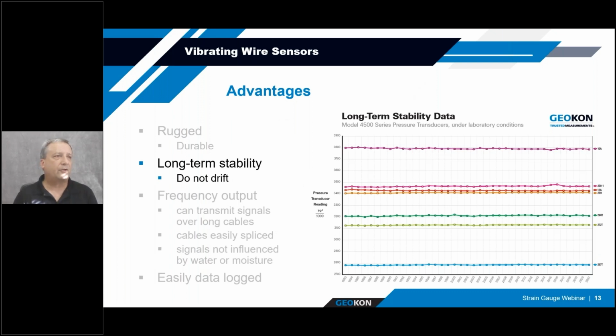Also, they're very stable for long term. Vibrating wires have been shown to provide significant or not changing output for quite a few years. We've got some sensors in the Geokon facility that have been read since the early 80s, shown here on this plot, with very little, if any, trend or drift over time. And we've got some case histories from installations that have been done for almost 40 years where there's been very negligible drift over time as well.